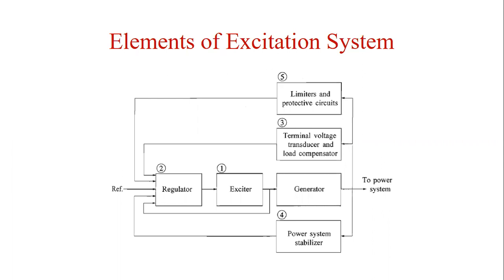The third part of the control circuit is the terminal voltage transducer and load compensator. It senses the generator terminal voltage, rectifies and filters it to a DC quantity, and compares it with a reference which represents the desired terminal voltage. In addition, load compensation may be provided if it is desired to hold constant voltage at some point electrically remote from the generator terminal, for example, partway through the step-up transformer.